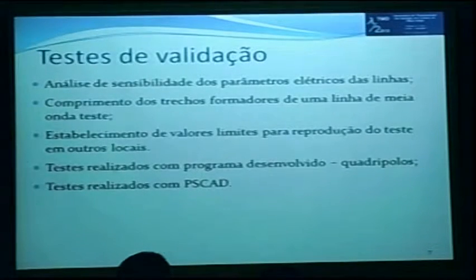Since this is an energization maneuver, our interest is first focused on the positive sequence. The first question that arises is how valid it is to use lines that are similar but not identical to represent a half-wavelength trunk formed by a single line with exactly the same characteristics. So we conducted a lot of sensitivity tests with the electrical parameters of the lines used in the test.